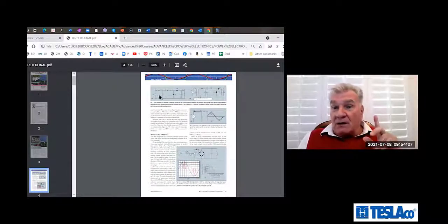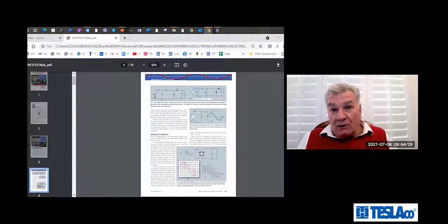Remember, I discussed why the step-up conversion is needed: varying AC voltage from 0 to peak and back to 0, the boost converter is such that it always steps up voltage. So power factor correction is basically changing the duty ratio in such a way that whether it's low voltage or peak voltage on the input, you always get a fixed voltage on your output. That's the definition of power factor correction.